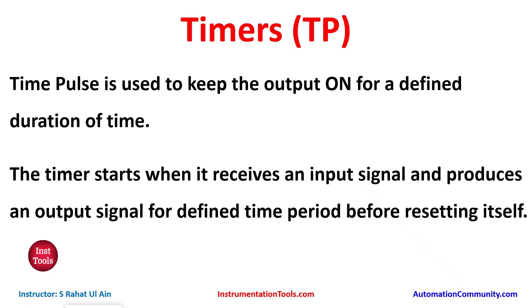Time Pulse is used to keep the output on for a defined duration of time. A timer starts when it receives an input signal and produces an output signal for a defined time period before resetting itself. It means when the input is on, the output should remain on for a certain period of time — for example, five seconds or one hour. In this case we use the timer known as TP, Time Pulse.